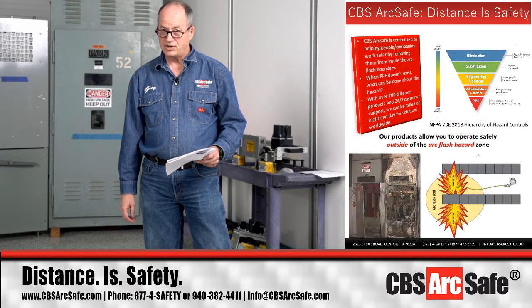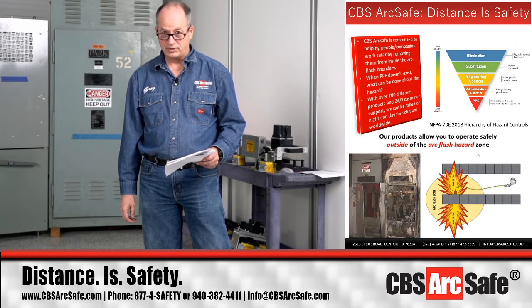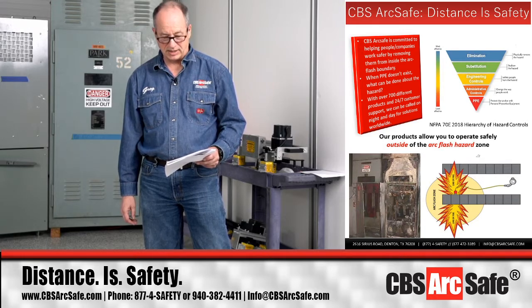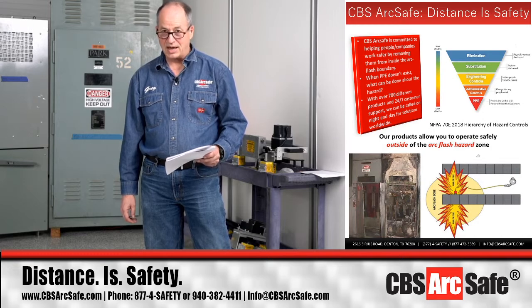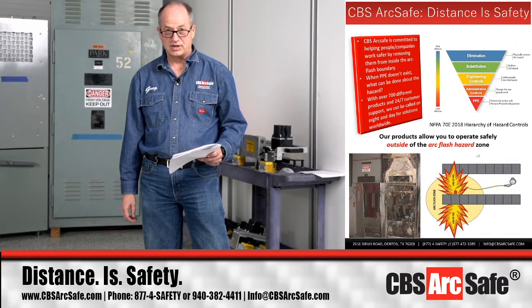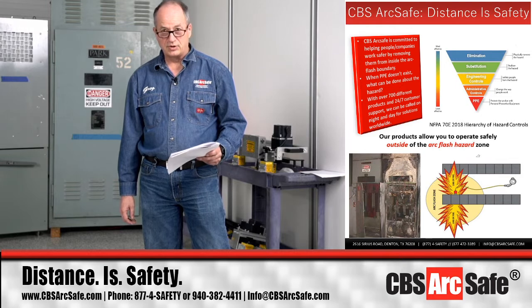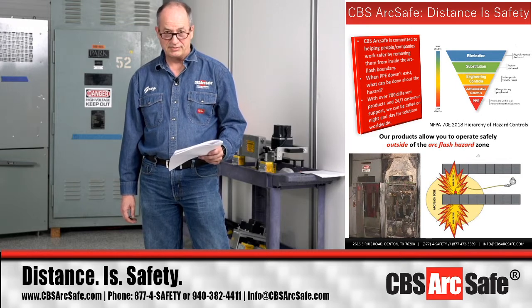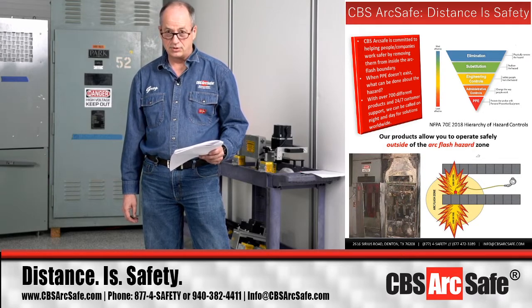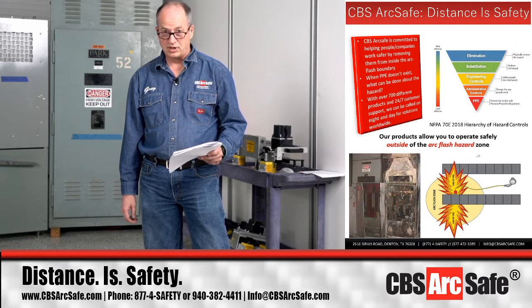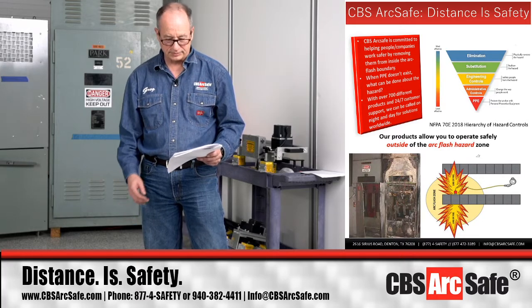CBS ArcSafe manufactures over 700 products to help people with remote racking and remote switching for arc flash mitigation, with the idea being to stay outside the arc flash hazard boundary when performing that operation. Our equipment works at the engineering controls level of the inverted pyramid shown on the slide, instead of down at the PPE level where you might be inside the arc flash hazard boundary. We can get you anywhere from 30 feet to 100 meters away from the switchgear, keeping you and your electricians or operators outside the arc flash hazard boundary.